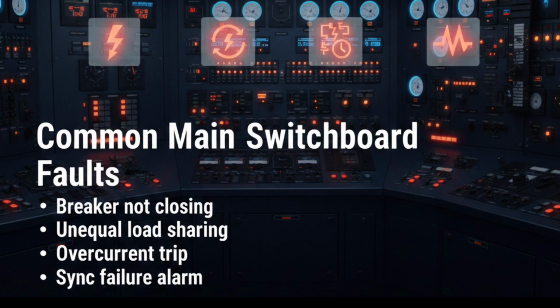Common main switchboard problems. Here you can see typical alarm indications on the main switchboard. Some of the most common problems on board are generator breaker not closing, unequal load sharing between generators, overcurrent trips, reverse power alarm, synchronization failure, and voltage instability. These faults may look complicated, but each one has a logical reason behind it. For example, breaker not closing could be due to voltage mismatch or protection relay active. Unequal load sharing may be due to governor or AVR imbalance. Overcurrent trip usually indicates excessive load or short circuit. The key point is, never randomly reset alarms. First understand the cause. Good troubleshooting starts with observation. Read alarm messages carefully. Check meters. Check indications. Logic first, action second.